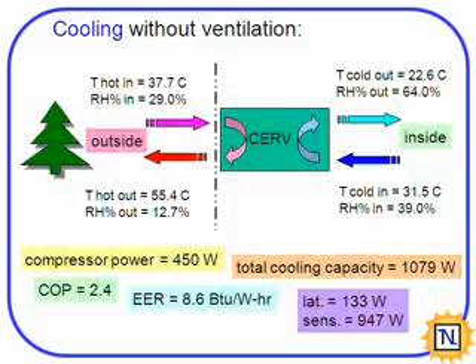Cooling without ventilation is the same idea as the heating. This would be like a window air conditioner in your house, where heating without ventilation is as if you took your window air conditioner and turned it around backwards. So here the compressor power is 450 watts. We're getting just over a kilowatt of cooling capacity. The outside air is coming in, adding heat to that, taking heat out of our inside air, and returning it cooler.